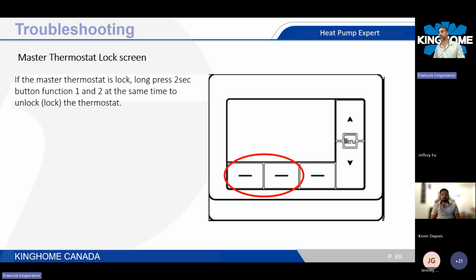You don't have to play with the wires. If that thermostat is locked, you see here there are two function buttons, function 1 and function 2. If you press both of them for a couple of seconds, it will lock the thermostat, and you will see a lock icon appear. If you click and hold them for another couple of seconds, you will unlock it. The homeowner doesn't have to know about this feature, so he will not play around with that thermostat. This one is only dedicated for you to work with.